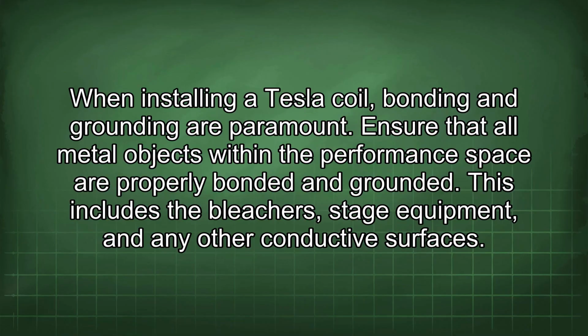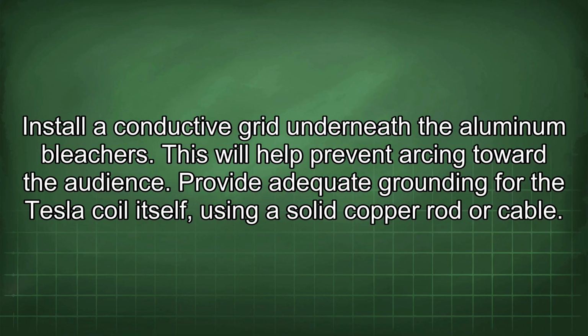When installing a Tesla coil, bonding and grounding are paramount. Ensure that all metal objects within the performance space are properly bonded and grounded. This includes the bleachers, stage equipment, and any other conductive surfaces. Install a conductive grid underneath the aluminum bleachers. This will help prevent arcing toward the audience.